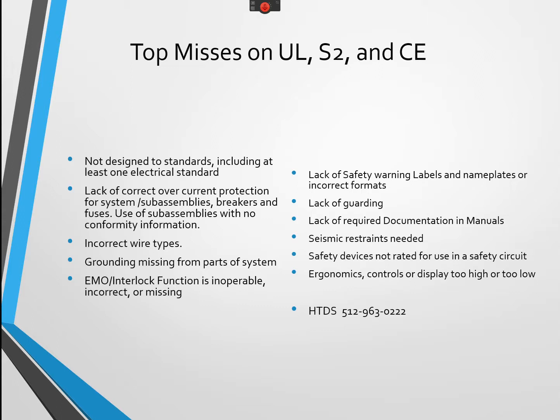That guarding comes in several different types. You've got fixed guarding, you've got removable guarding, you've got guarding with hinges and interlocks, and the labeling and how they're fastened and everything is important. Note that nowadays, going forward, guards and enclosures must use captive screws, meaning you don't pull the screw out and set it down and then put it back in with 2 of the 10 screws in place.